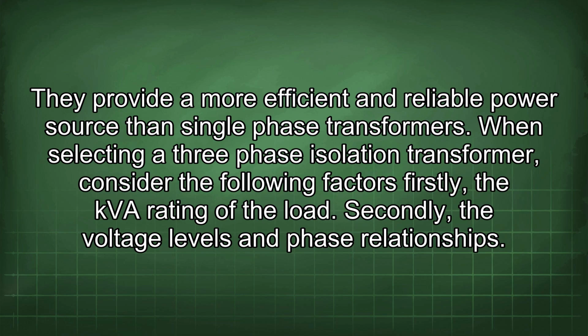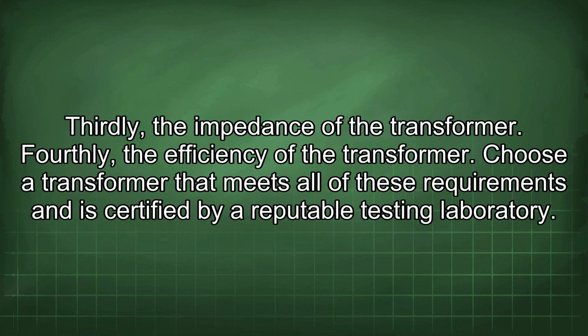When selecting a three-phase isolation transformer, consider the following factors. Firstly, the kVA rating of the load. Secondly, the voltage levels and phase relationships. Thirdly, the impedance of the transformer. Fourthly, the efficiency of the transformer. Choose a transformer that meets all of these requirements and is certified by a reputable testing laboratory.